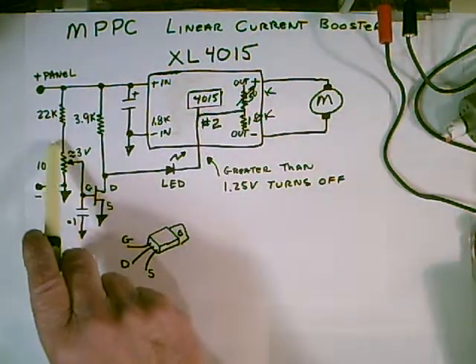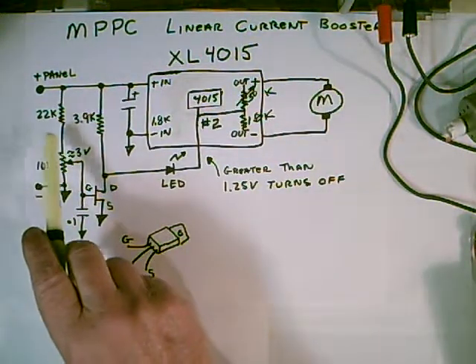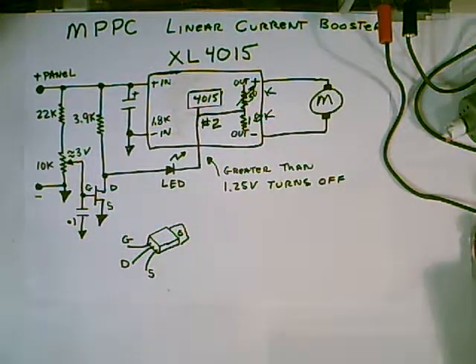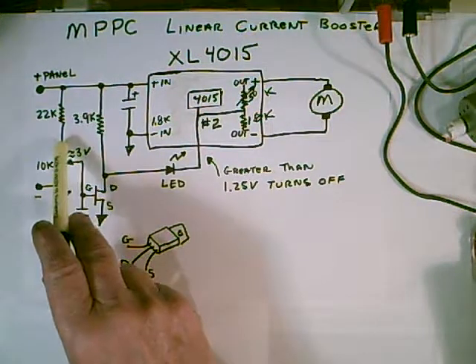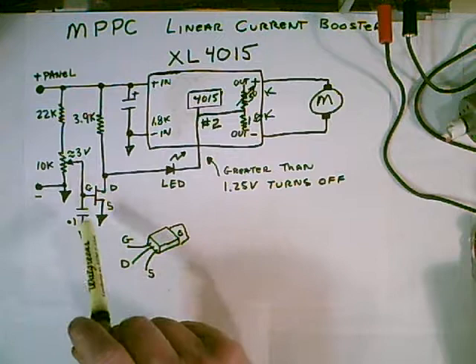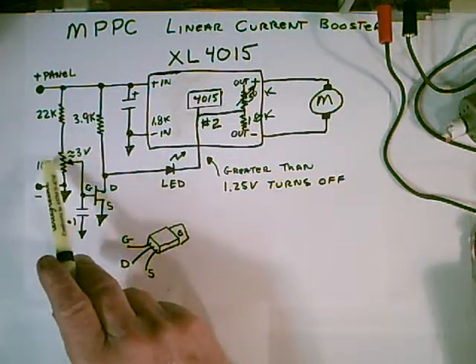So remember, you want to keep your panel at the power point voltage. That's usually listed on the back of the panel. There will be the maximum voltage that it will put out, and then there will be the maximum power point voltage. And you want to set the voltage for somewhere around there.